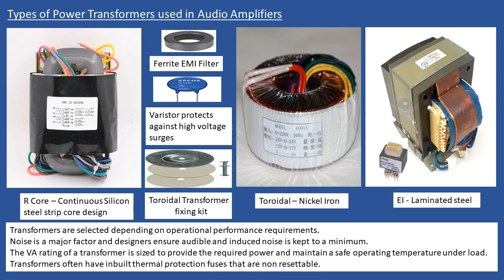And what the manufacturer has done there is they've just embedded that or put that into the power transformer as standard. Or you may wish to purchase these from any electronic supplier, and you just clip it onto the power cable, and then any electromagnetic interference which is being passed through those power cables would be absorbed by the EMI filter. And equally so, if any electromagnetic noise is being generated from the transformer, then as it passes out of the amplifier, again it would be absorbed as well.